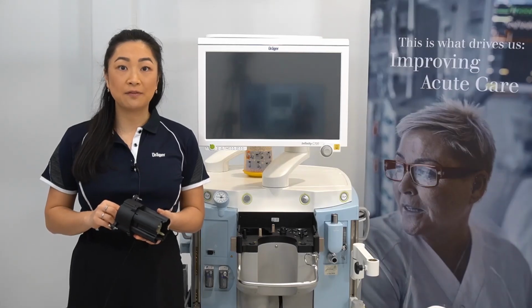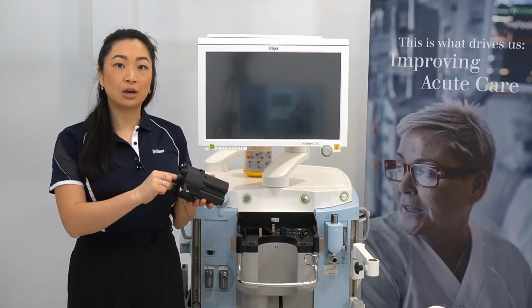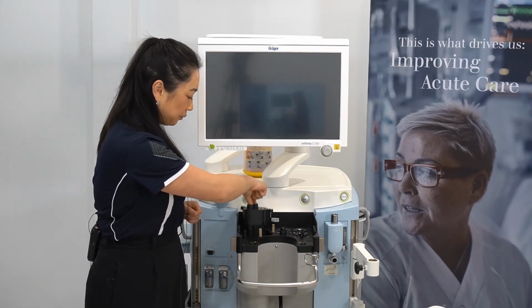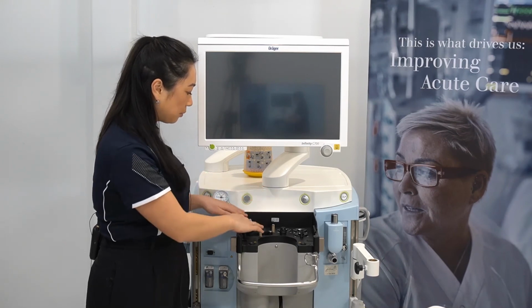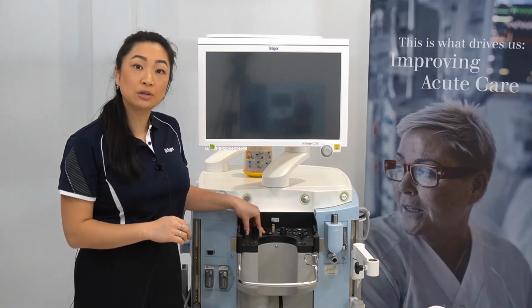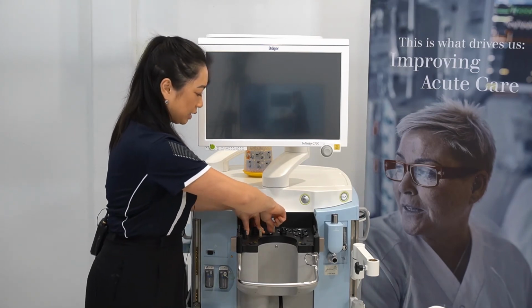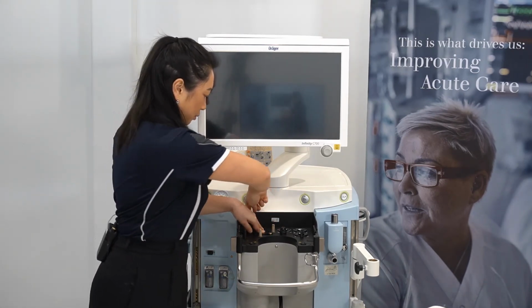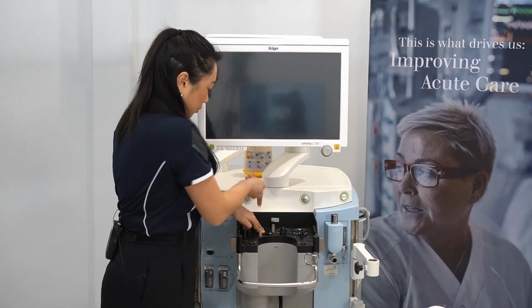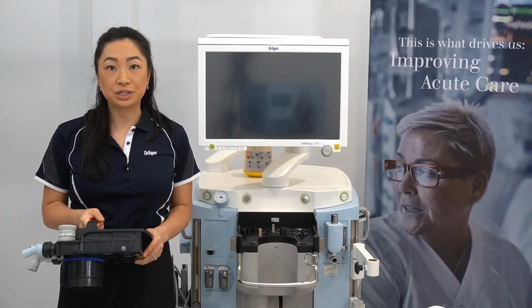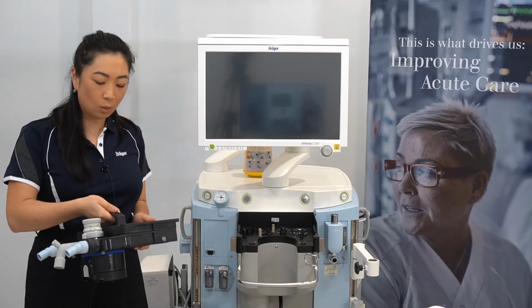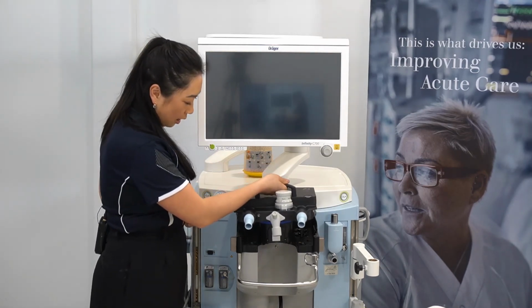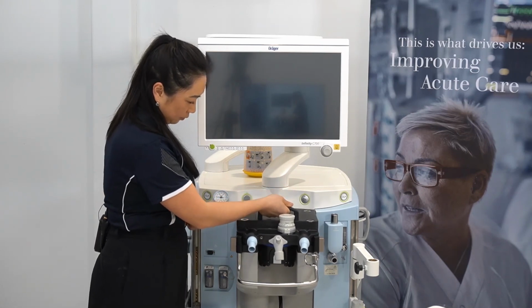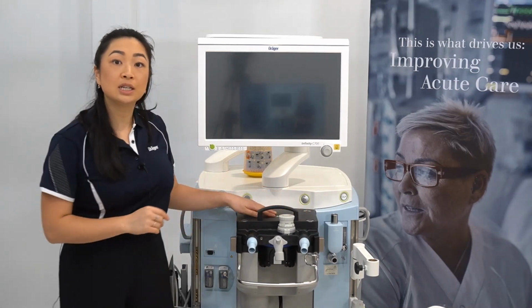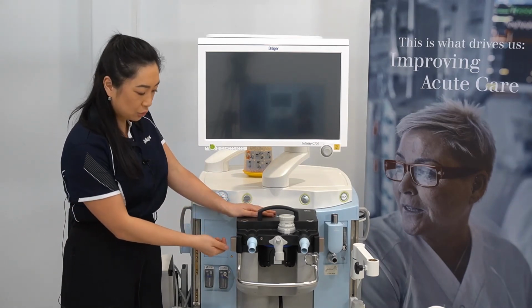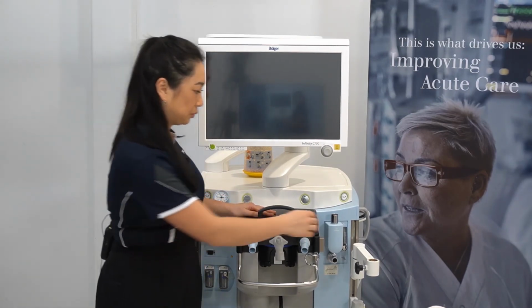To return the turbine ventilator, place the finger into each of the holes, align it in position and place down. Then push down on the 2 screws and turn as you go to lock it into position. To return the breathing system to the device, one hand on the handle, align it up into position and push down. Then to lock it into place, turn the lateral twist locks from vertical to horizontal.